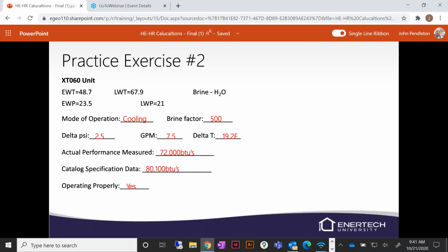If it's not keeping up for some reason, then you may want to dig in a little bit deeper, but normally we don't size units that tight. So hopefully it's not because it's not keeping up. If that's the case, we'll have to dig into it a little bit deeper. But hopefully, we can just wait 6 more months. It'll roughly be the same. Hasn't dropped anymore. But I definitely, in this situation, make a note on your ticket to double check that again later on down the line, 6 months or so.